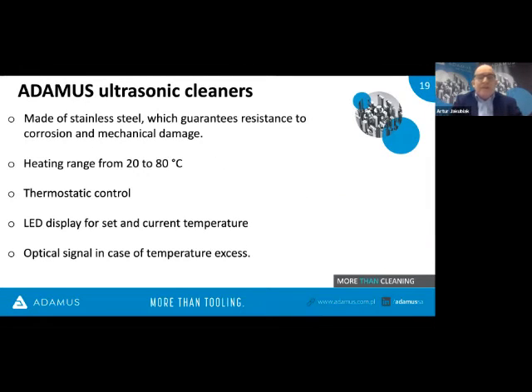Generally, the tanks are made of stainless steel, which of course guarantees resistance to corrosion and mechanical damage. We have a heating range from 20 to 80 Celsius. As you saw before, this is absolutely enough for the cleaning. We have a thermostatic control, which I already mentioned. We have an LED display for the set and current temperature. And of course, an optical signal in case the temperature exceeds the set value.